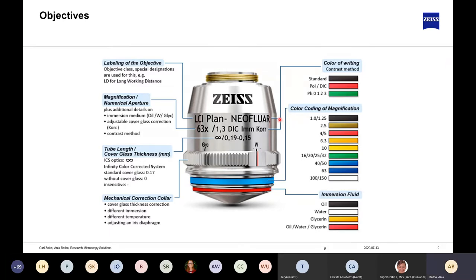The second thing you see is the name of the objective, which tells you what the objective can be used for. For a normal student microscope it would say A-PLAN, standing for Achroplan objectives. On an inverted microscope, the objective might have 'LD' (long-distance) in front because the distance between the objective and sample is longer than on a compound microscope. 'PLAN' means additional lenses have been added to create flatness of the field of view.